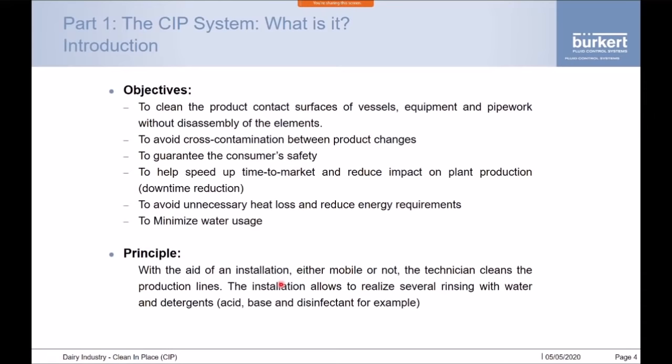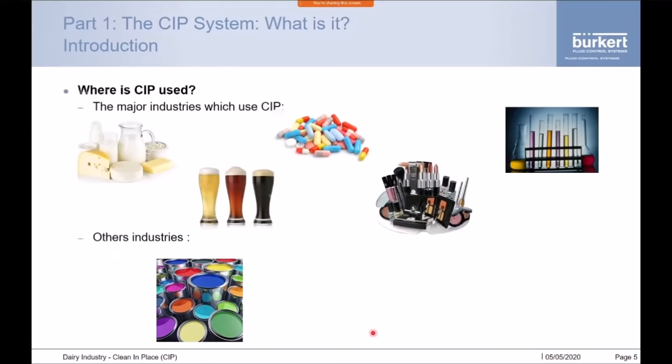The principle is that with the aid of an installation — now that can be fixed or mobile — the technician cleans the product lines in any pipes or vessels that are attached, using several different stages along with rinsings. The stages typically use an acid or a base and a disinfectant, interspersed with several rinsing cycles to make sure lines are nice and clean. Industries that use CIP include dairy, brewery, pharmaceutical, and cosmetics.